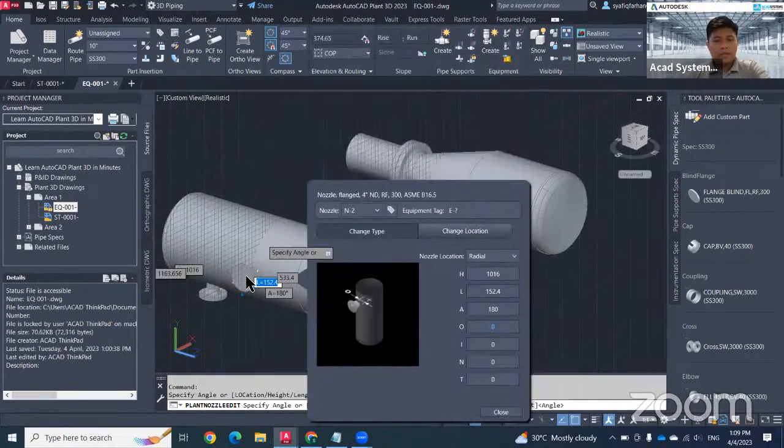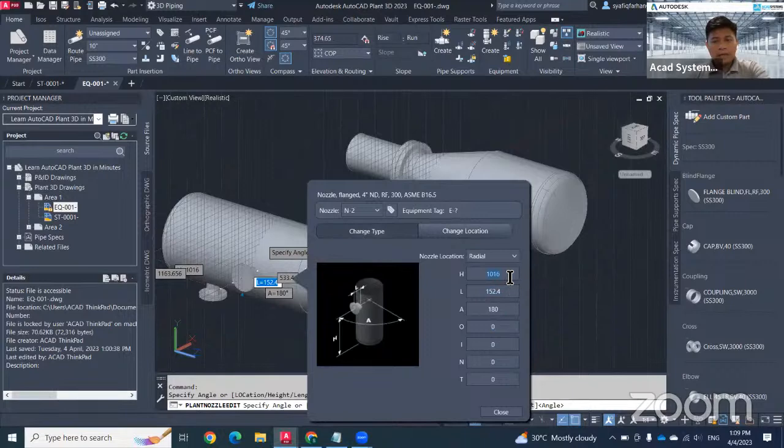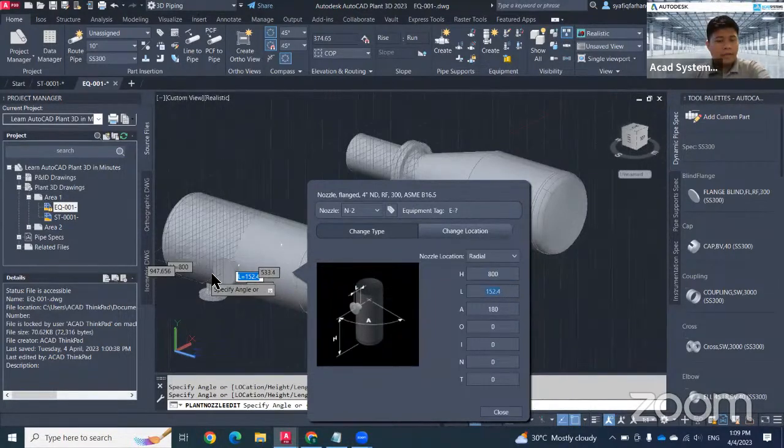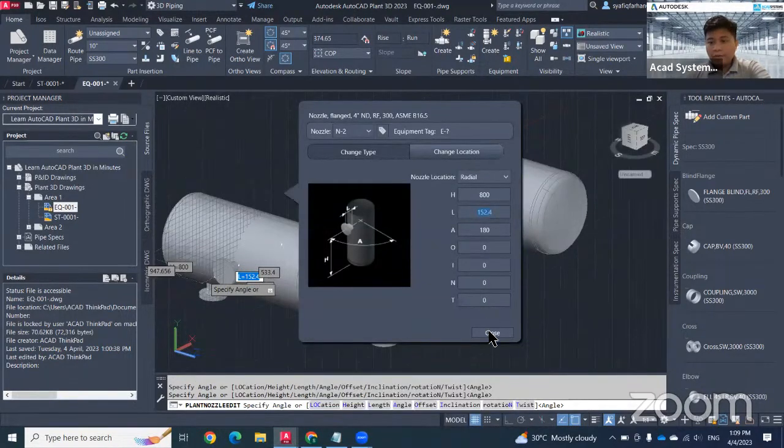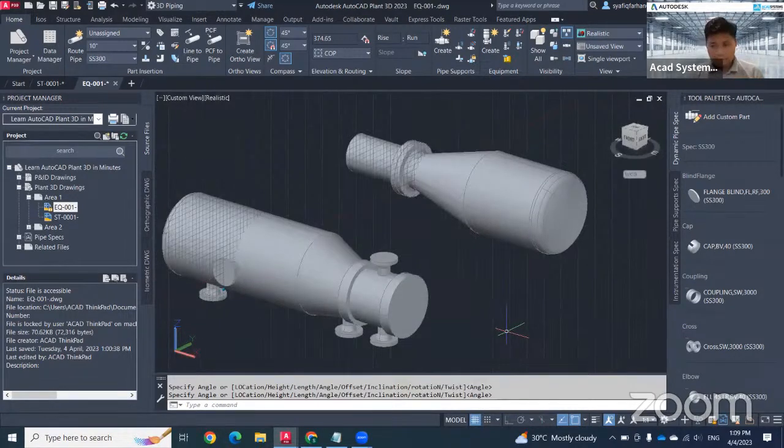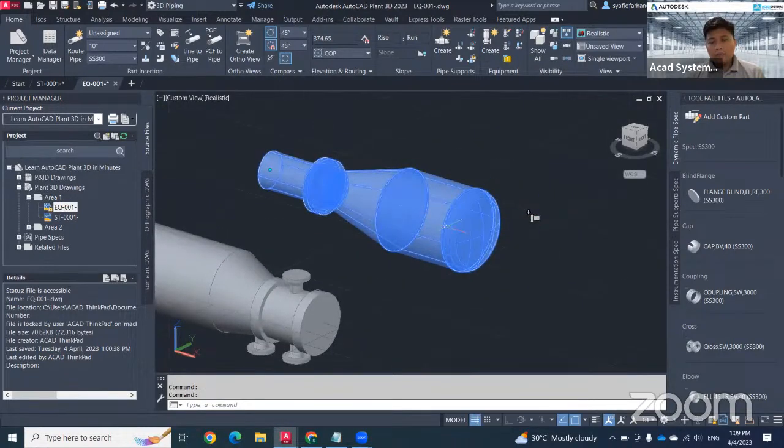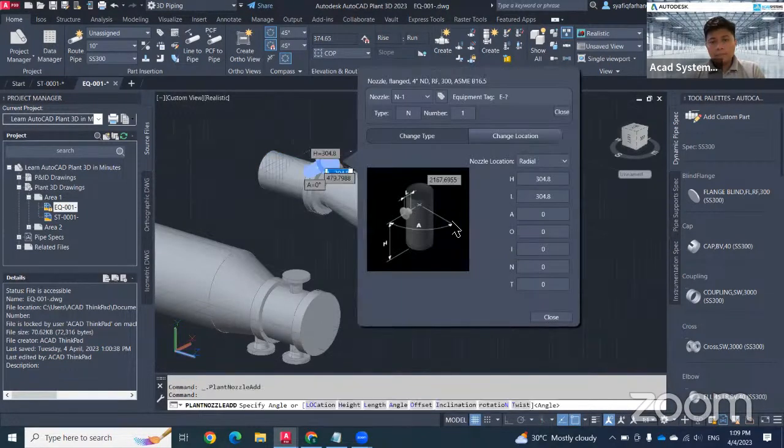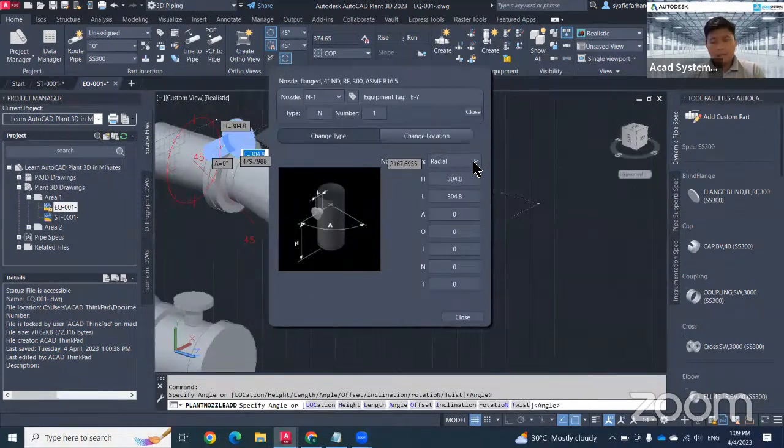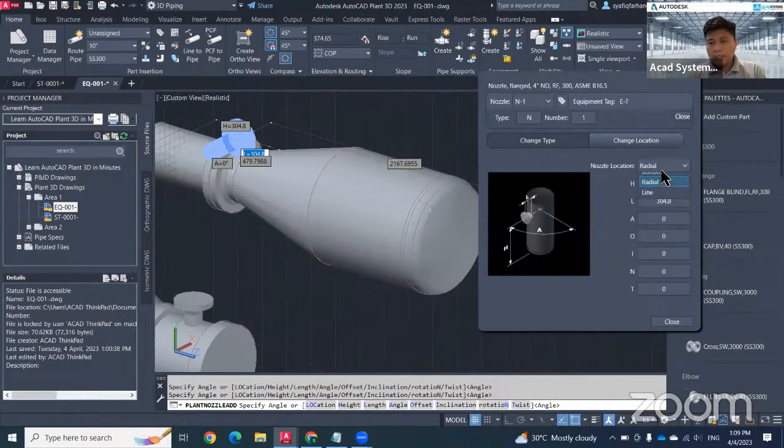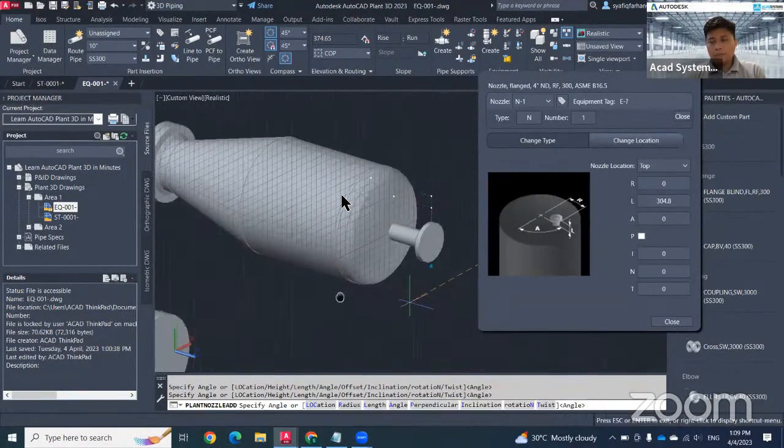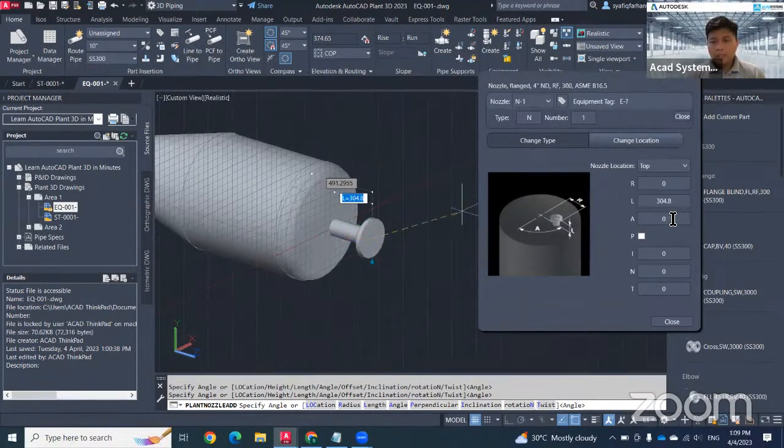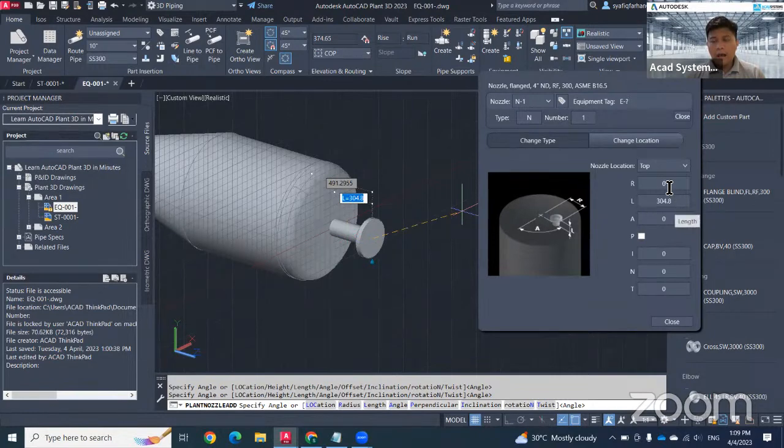It will go directly to here. If I plan to change the distance or length, I can go to here, this height, I can change here to 800. That will be the difference on how to change the nozzle if you are using the predefined shape like pump or a tank. To create a new nozzle, you can go to this first object and hit add nozzle. By default, this nozzle will be radial. In case I want to insert as top or bottom, I can change to top. This will be the location of top area. You can also change the angle, the A and R value, and together with the length.